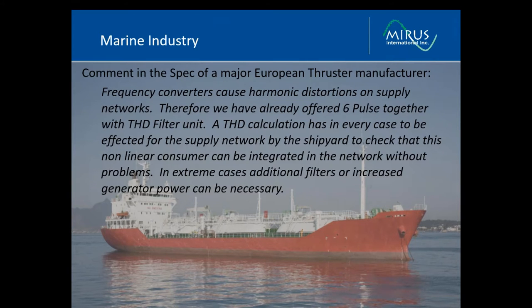This clause came from the technical specification of the European thruster manufacturer. In their instructions, they state that although they supply a passive harmonic filter, in extreme cases, additional filters or increased generator power can be necessary. This is evidence that harmonic mitigation is needed, and if the right passive filter isn't selected, problems may persist, including the addition of extra filters or increased generator power. And I can assure you, and you'll find out in the presentation today, that there are good filters available that can meet these needs without these conditions.